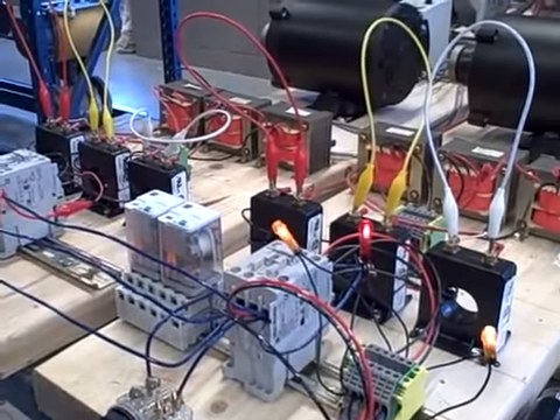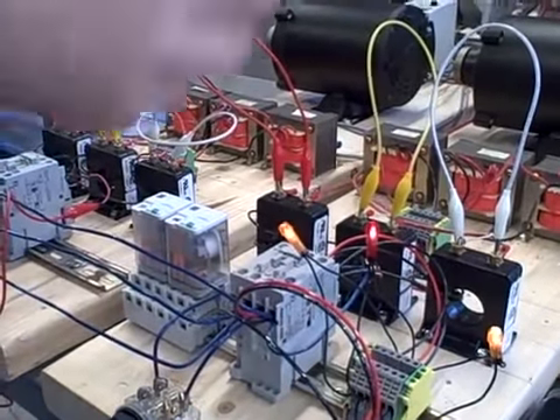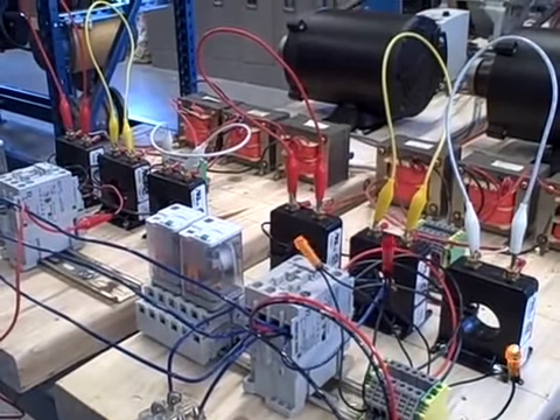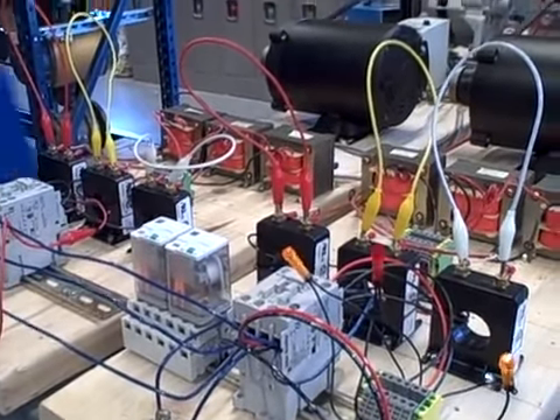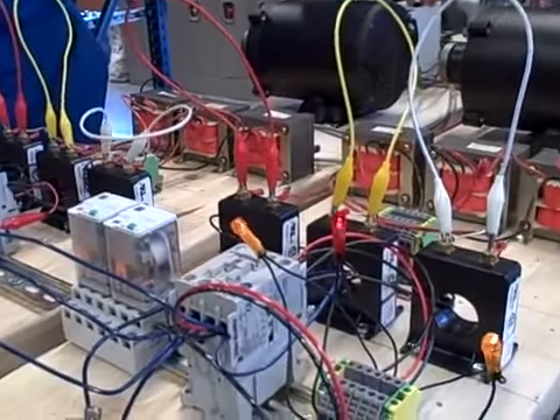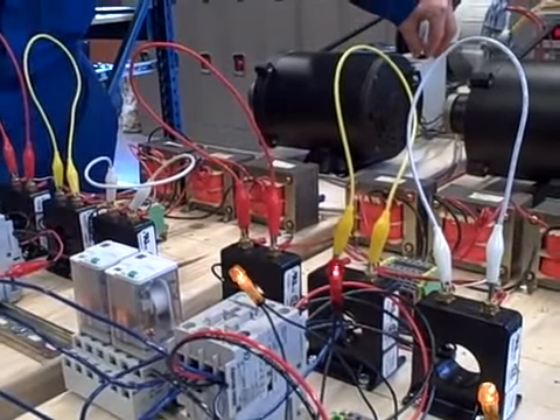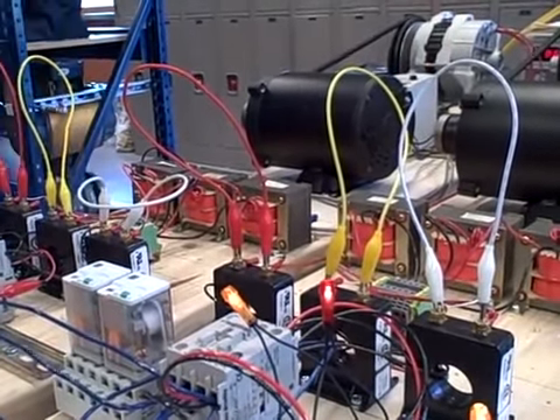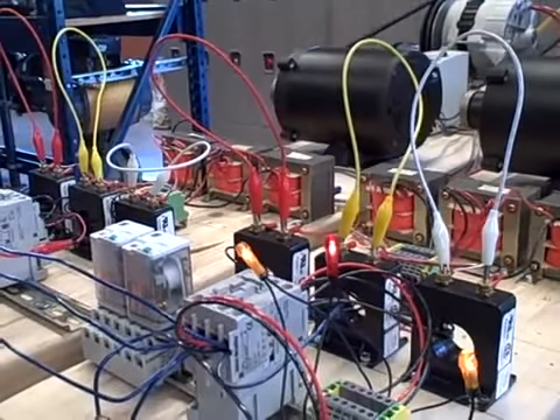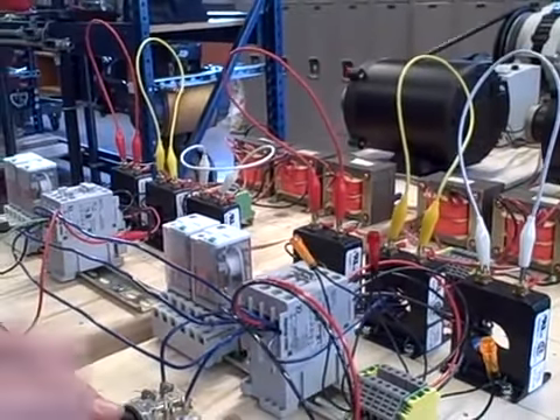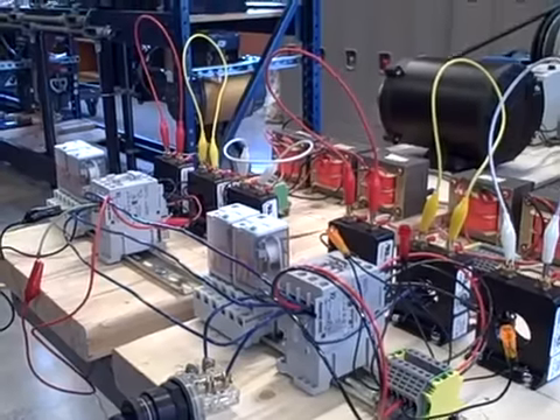I don't want to close them when I have light, because that would be closing a breaker across a substantial voltage difference, and that would be a transient event, a current that would shock the generators. I'm going to speed this generator up a little bit. And now they're parallel with each other.